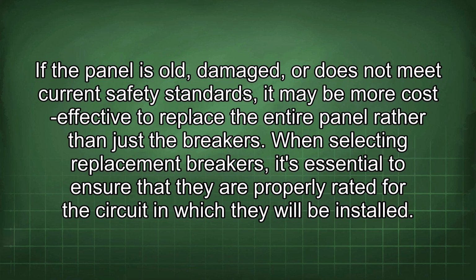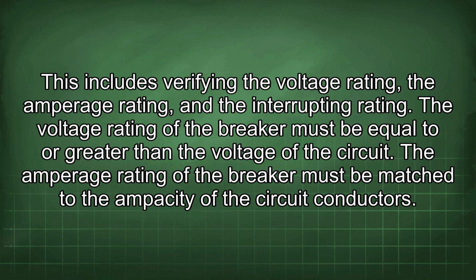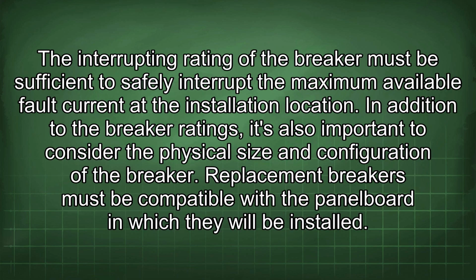When selecting replacement breakers, it's essential to ensure that they are properly rated for the circuit in which they will be installed. This includes verifying the voltage rating, the amperage rating, and the interrupting rating. The voltage rating of the breaker must be equal to or greater than the voltage of the circuit. The amperage rating of the breaker must be matched to the ampacity of the circuit conductors. The interrupting rating of the breaker must be sufficient to safely interrupt the maximum available fault current at the installation location.